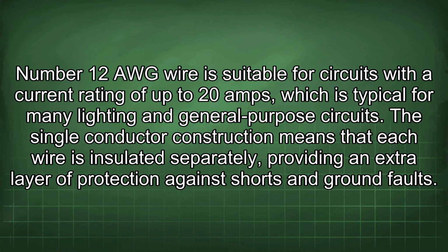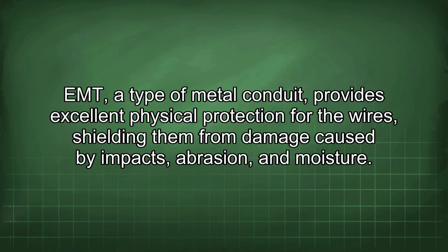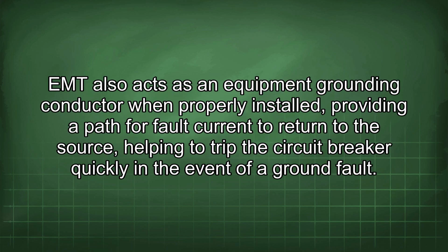The single conductor construction means that each wire is insulated separately, providing an extra layer of protection against shorts and ground faults. EMT, a type of metal conduit, provides excellent physical protection for the wires, shielding them from damage caused by impacts, abrasion, and moisture. EMT also acts as an equipment grounding conductor when properly installed, providing a path for fault current to return to the source, helping to trip the circuit breaker quickly in the event of a ground fault.